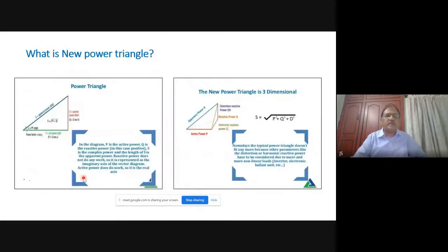I'll explain this to you, but before I explain the energy saving using management of harmonics, I want to introduce you to a new power triangle concept. We all know that kVA is equal to the square root of kilowatt square plus kVAR square. We know this power triangle relationship. But the new power triangle takes into consideration displacement power factor as well as distortion power factor caused by the harmonic. So in the new power triangle, kVA is equal to the square root of kW square plus kVAR square plus distortion power square. Now we have meters which are capable of measuring all 3 parameters and arriving at the true power factor and therefore the kVA.